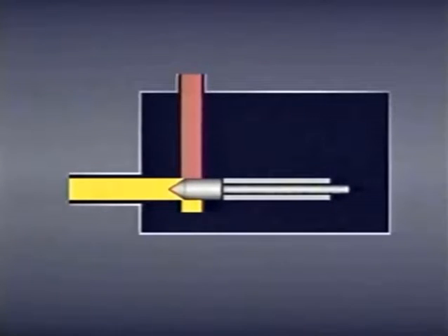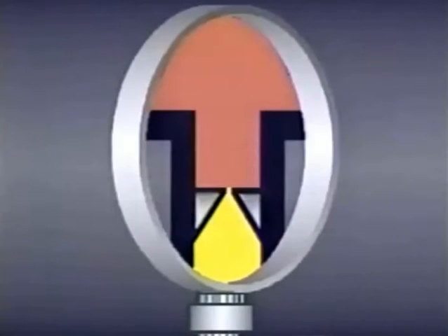The opposite is true if the fluid is cooler than normal. The rod contracts, increasing the orifice size. Because the cold fluid has a higher viscosity and does not flow as easily, the same amount of fluid passes through the orifice. More commonly, flow control valves use a sharp edge orifice for temperature compensation. Within limits, this type of orifice ignores differences in viscosity.